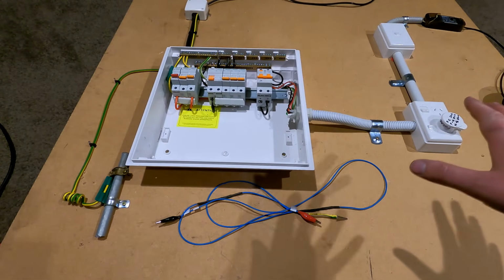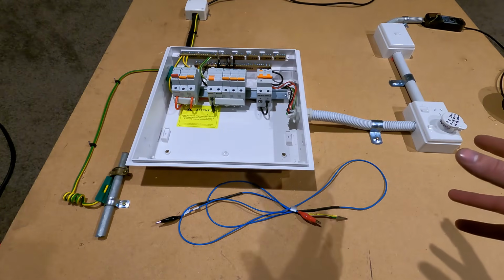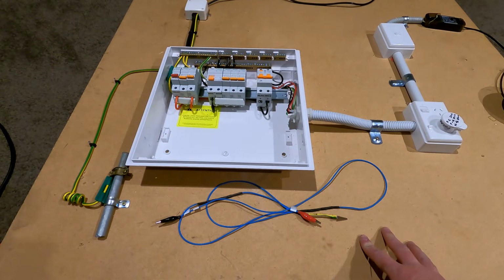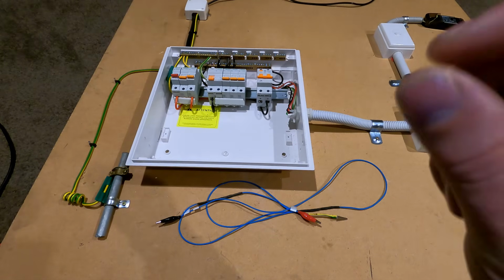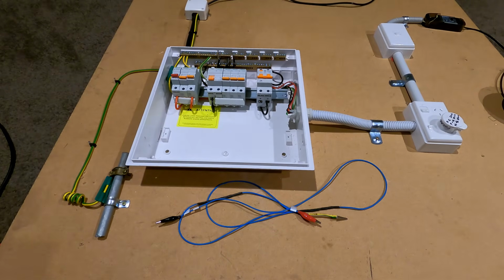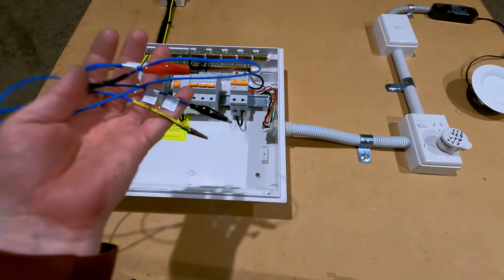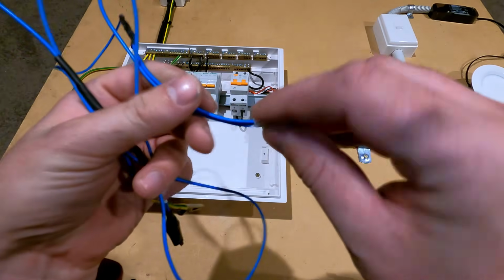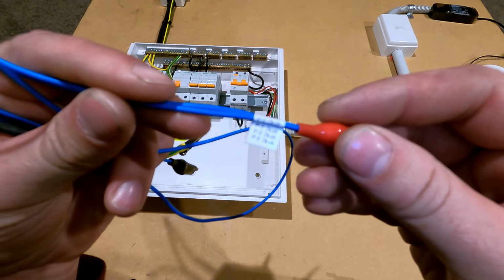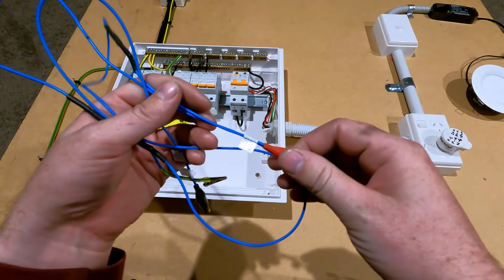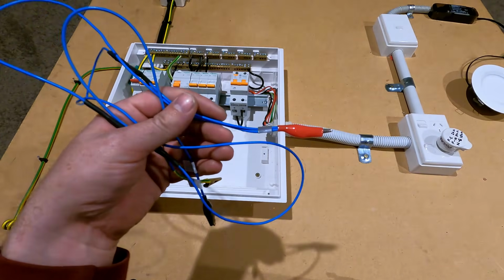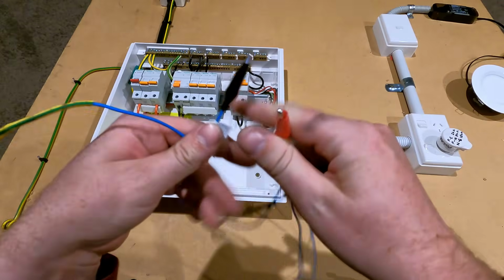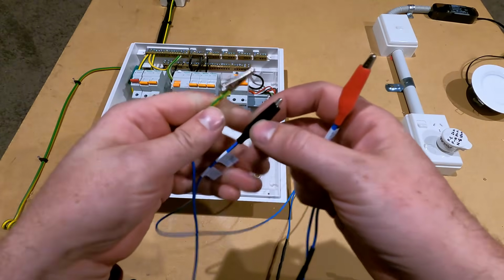The only light fitting types that the regs would be concerned about are metallic ones or Edison screw fittings. Now you'd have to verify your neutral is on the outer side and the phase is right in that middle part of the Edison screw. Now this cable here is the same known resistances. I've got them on wee tags so I can tell if I do forget. It's probably blurry on the camera here. As you can see, red, black, green, phase neutral, earth.